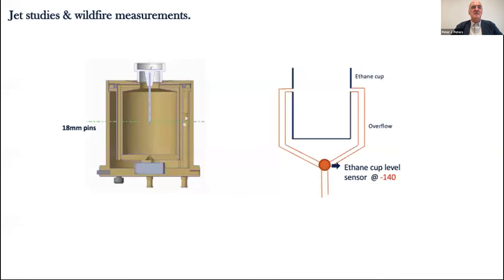So the principle of the jetting, you can see here a little bit. We have the jet stream coming from the bottom, and it goes to both sides, as you can see here. The ethane level is here, and we jet in this particular area. Immediately after we have jetted the grid or the loop, we bring it down for more cooling. Once it is cool, we take it out, and immediately bring it to the liquid nitrogen.